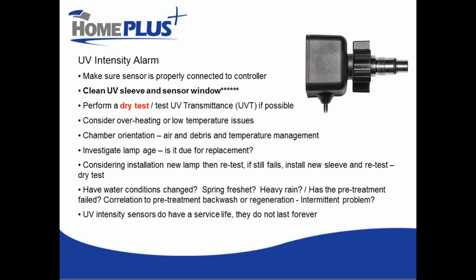So some other things to consider, especially if you have problems repeatedly with intensity issues. Consider whether or not you have temperature management related problems. Is there any other equipment in the room that is causing excessive heat, or an exhaust fan from something blowing right on your UV sterilizer? We had somebody once who did a really nice job of insulating all of the pipes in their water treatment room, but they decided to also insulate their water treatment chamber, which allowed no cooling of their chamber, caused everything to overheat, and had lots of intensity alarms because the lamp output dropped.